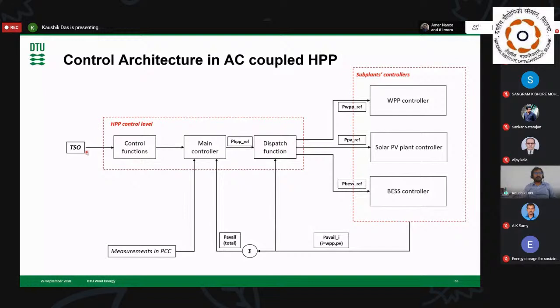Then you have a hybrid power plant controller, which traditionally gets control functions from the TSO, same as a wind or solar power plant controller. Most of the time it operates in maximum power point tracking mode, but sometimes it gets a signal for balance or delta operation, where reserves must be kept because of network congestion, or to provide grid services like frequency services. Then we have a main controller and dispatcher, which dispatch to the individual wind power plant, solar power plant, and BESS controller.